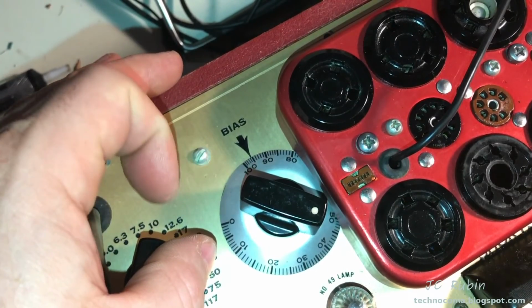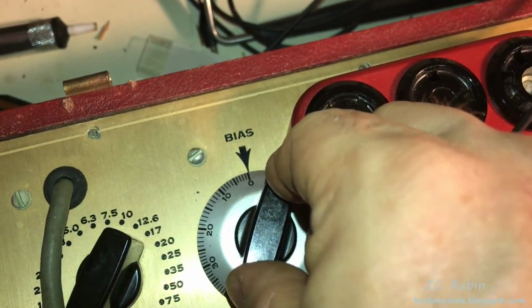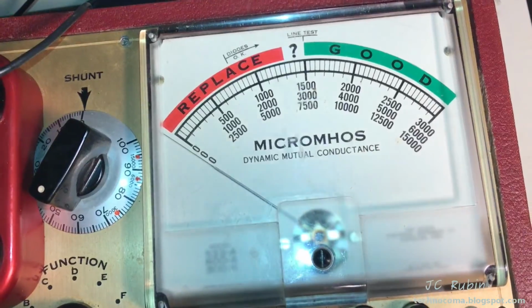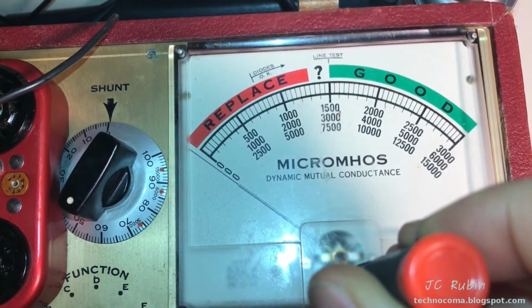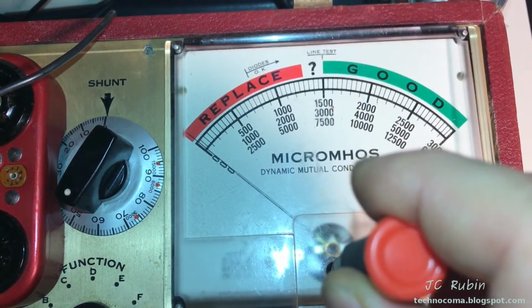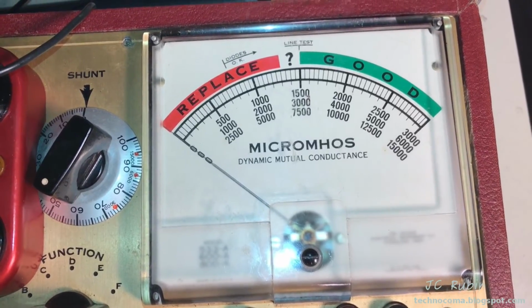So there's a screw right here. I'm just going to make that adjustment right quick because I know that that's wrong. And there we go. Stops at 0. Stops at 100. I'm going to go out on a limb here before I start anything and say that the static 0 should probably be here. I think I'm just going to set that.